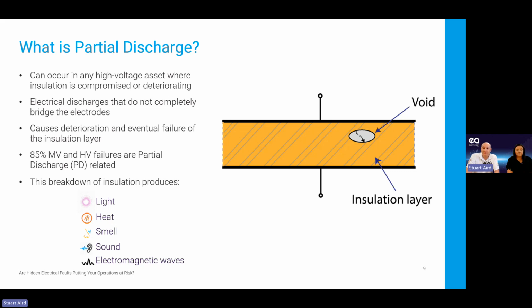It will have smell. So if you go into a substation that's got high levels of partial discharge active within there, you will get a really strong ozone type smell. Things like old paper, what photocopiers used to smell like, that type of smell, really strong ozone type smell in the substation. If that's the case, you might want to just turn around and leave that substation, because it's probably in a really bad condition. Sound as well, so you can hear PD, you hear that crackling type sound from partial discharge.